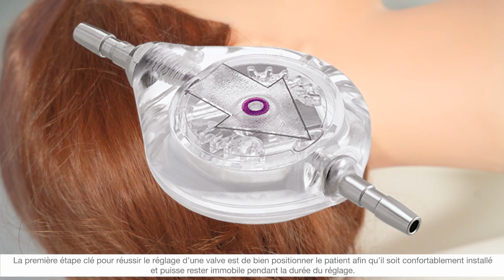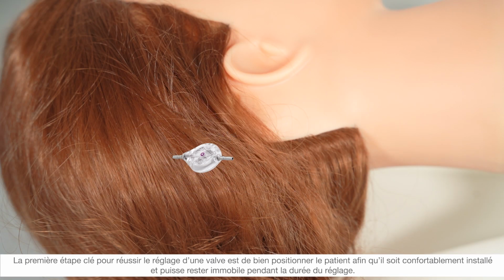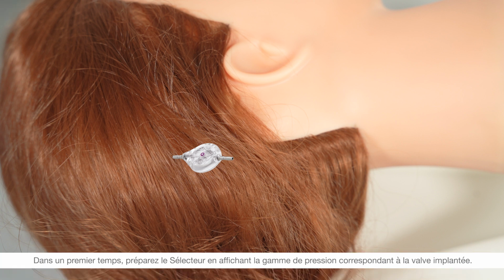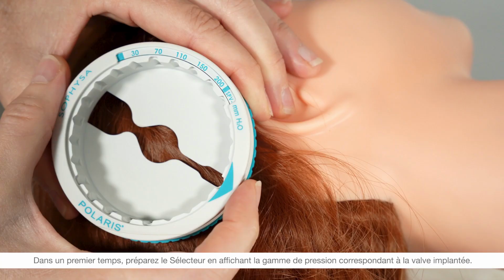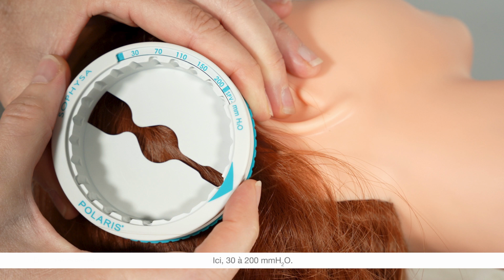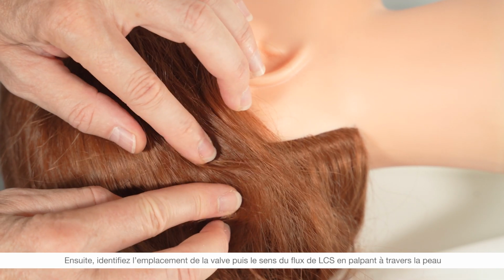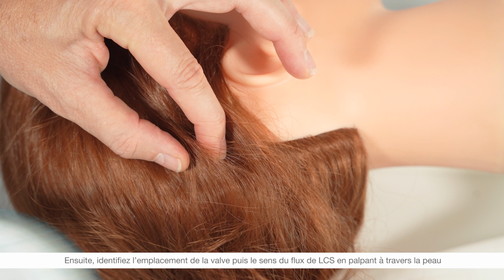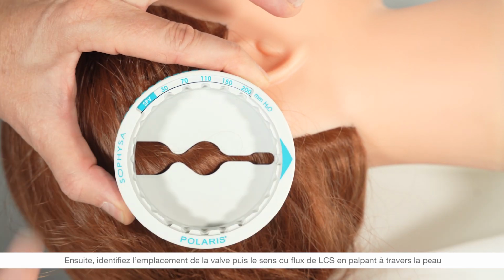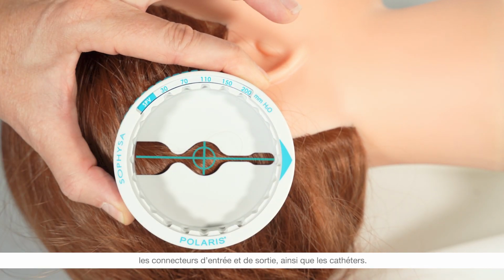First, position the patient in a comfortable way that also allows an easy access to the valve implantation site. Next, prepare the locator by selecting the correct pressure range to match the implanted valve. Here, it is the 30 to 200 mm of water range. Palpate the patient's valve implantation site in order to determine both the location and orientation of the valve. Using the inlet and outlet connectors as guides can be helpful.